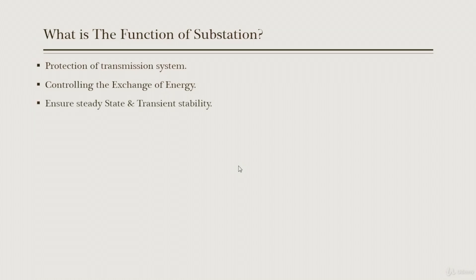The substation ensures steady state and transient stability — both very large and important fields. Steady state stability represents the stability of the power system when it supplies a constant amount of power. Transient stability represents the behavior of the system when disturbances happen — whether our system can sustain those disturbances or not — including load shedding and prevention of loss of synchronism.